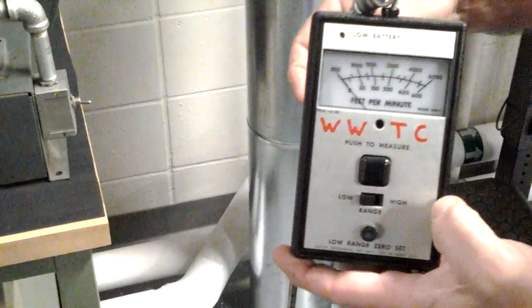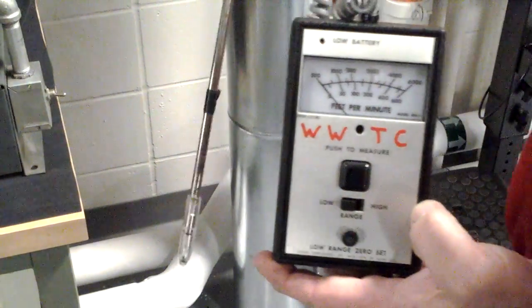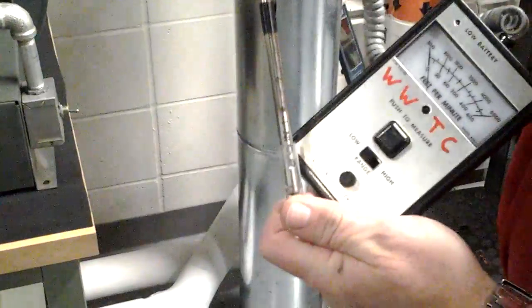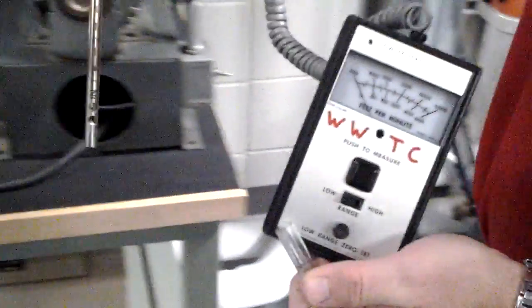The unit is now ready to take measurements. To take a measurement, remove the probe tip cover and either insert the probe into the duct through a 3/8 inch or larger hole, or hold the probe in the airstream to be measured.